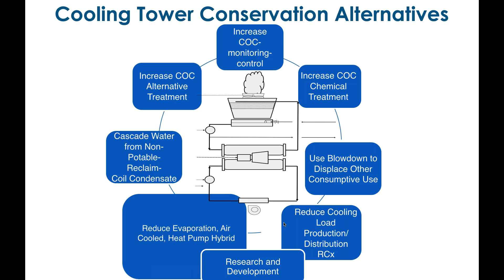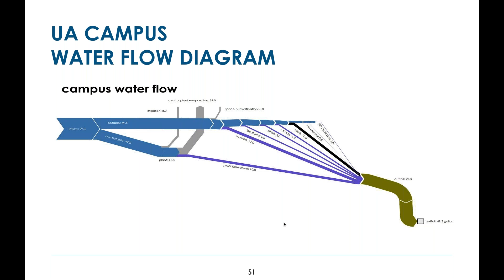One way it's going to potable water to the buildings, and then that comes out as water going to drain to the sewer, showers, toilets, urinals, all that kind of stuff. That's going to the drain. I gotta go back up. And then the other half splitting there, you see part of it going down. The purple at the very bottom is the plant blowdown. The gray that's poking its way up, that's the evaporation. All of this, with the exception of the evaporation, is going to the county sewer system now.